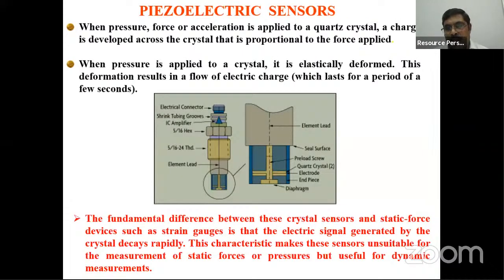The next one is the piezoelectric type sensor. This is a very, very special type of sensor. In this sensor, there is a piezoelectric type crystal. The special property of this crystal is that when you apply any external force over it, it will induce an EMF. The induced EMF from the crystal will be directly proportional to the external force. So by making a correlation between the induced EMF and the external force, the pressure can be measured. One special characteristic of the sensor is that the EMF produced from the sensor will decay within a fraction of a second. The EMF will disappear. Therefore, this sensor is mainly meant for measuring the transient pressure. If you are using it for static pressure, of course you will end up with a wrong value. Again, this is a very good sensor and cost effective.